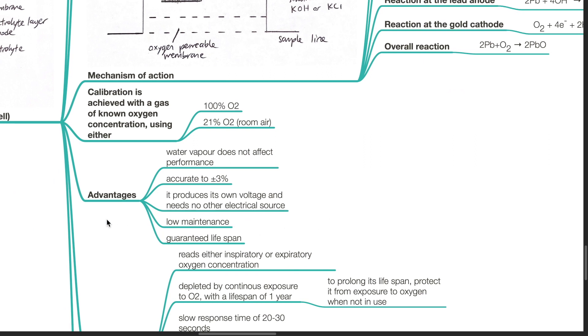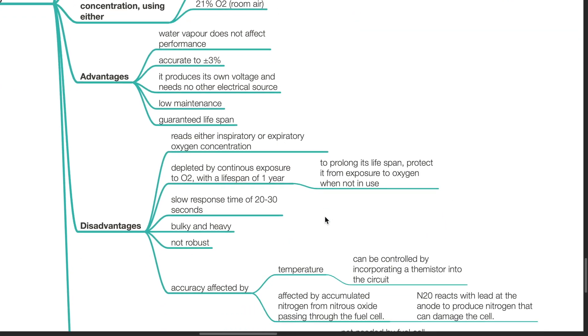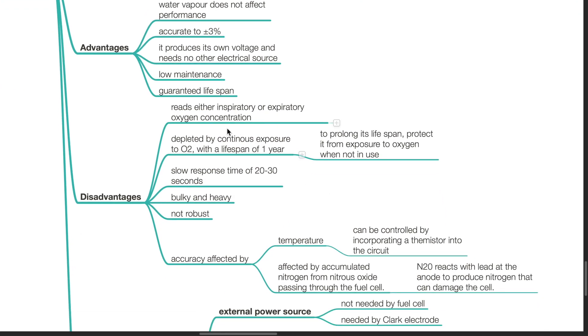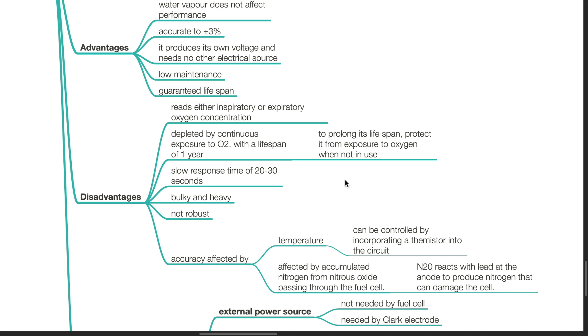Advantages of the fuel cell: water vapour does not affect its performance, it is accurate to ±3%, it produces its own voltage and needs no external electrical source, and it has low maintenance and a guaranteed lifespan. Disadvantages: it reads either inspiratory or expiratory oxygen concentration, and it is depleted by continuous exposure to oxygen with a lifespan of 1 year. To prolong its lifespan, protect it from exposure to oxygen when not in use.